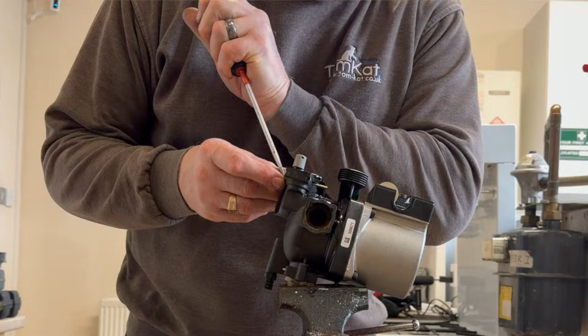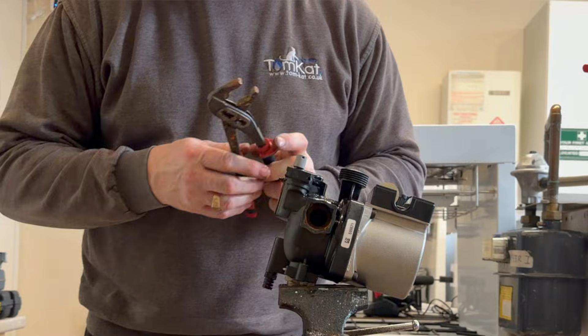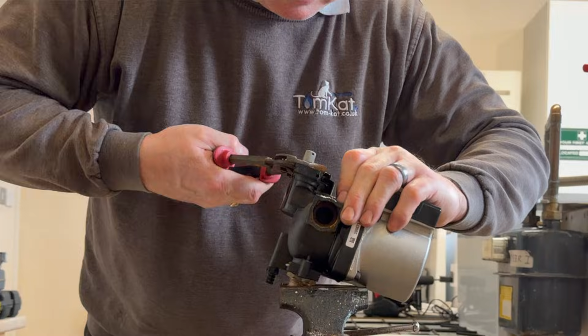Now, first thing I'm going to look at on the back of the pump is the auto air vent. This is going to get a spray with the old WD first. Now I need to remove this clip, and then get the grips on it, see if we can get it to come out. There you go.